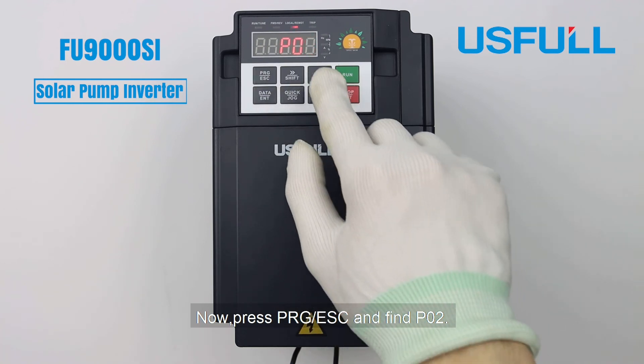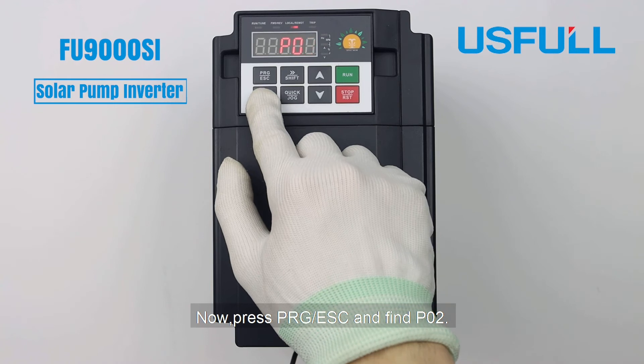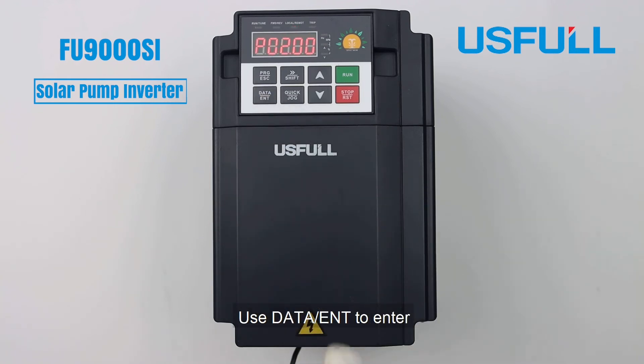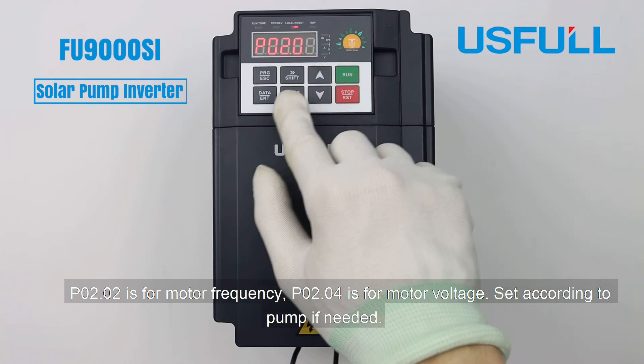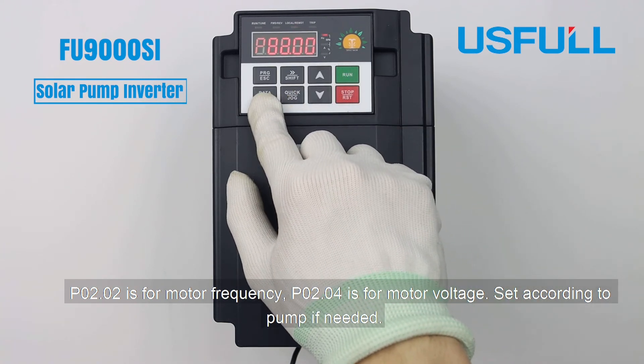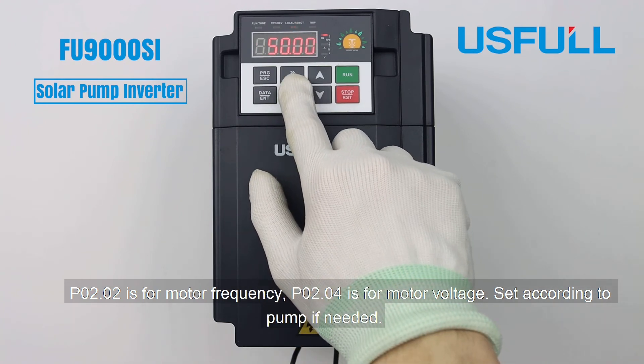Now press PRG and find P02. Use DATA/ENT to enter it. P02.02 is for motor frequency and P02.04 is for motor voltage. Set these according to your pump if needed.